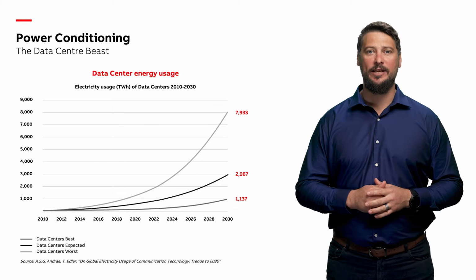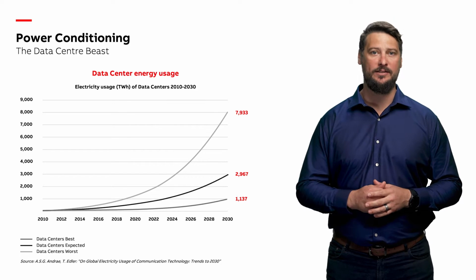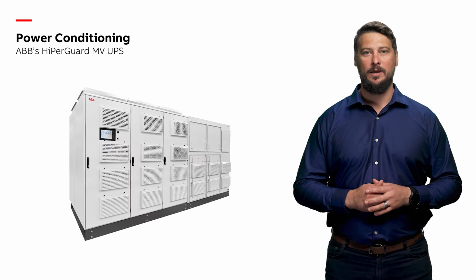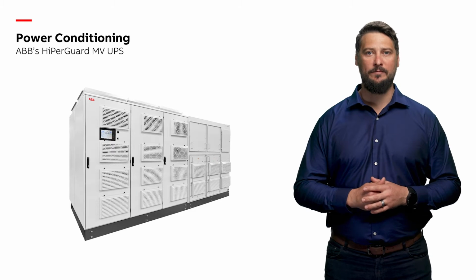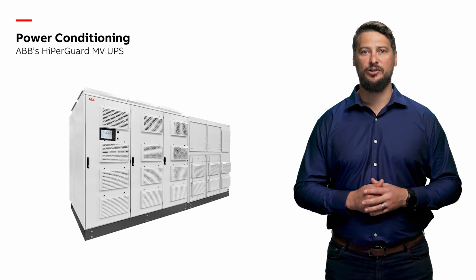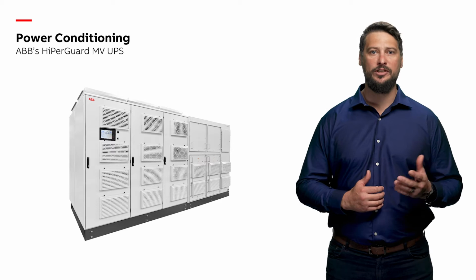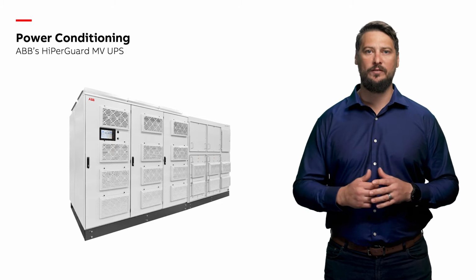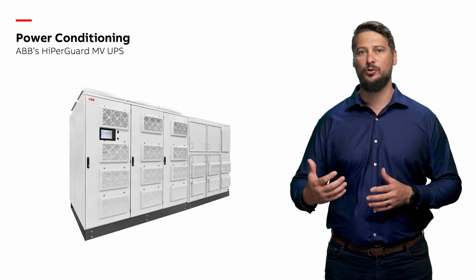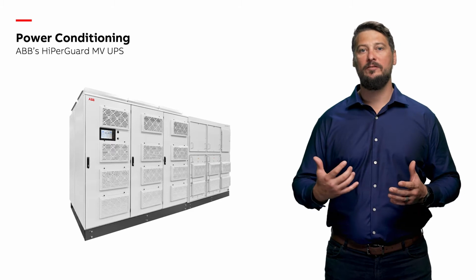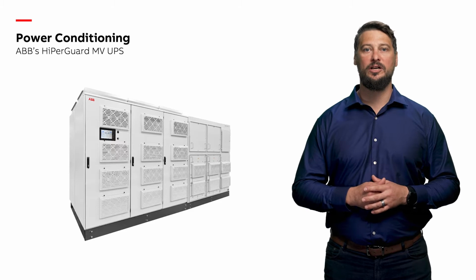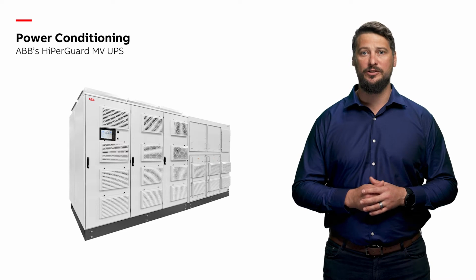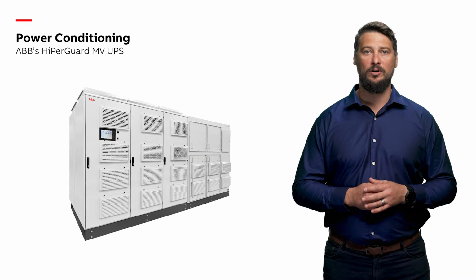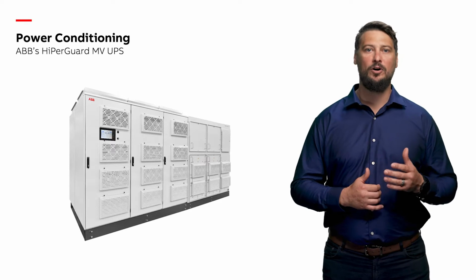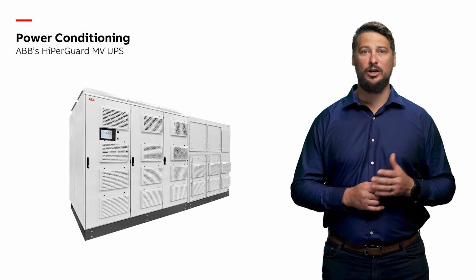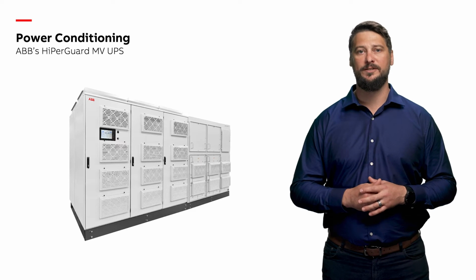Data centers are already significant in relative energy storage capacity. Can they do more for the grid? Introducing ABB's HiPerGuard MV UPS, the next generation power protection for data centers. The shift from low voltage to medium voltage represents a natural evolution in the power protection for substantial critical power facilities. A key advantage lies in significantly lowering costs associated with facility construction and operation. This is achieved through larger protected load blocks, a reduced switchgear count, and minimised size of busways and cabling, resulting in lower losses and higher overall efficiency.